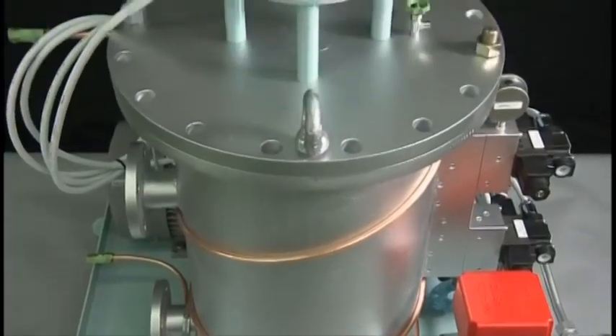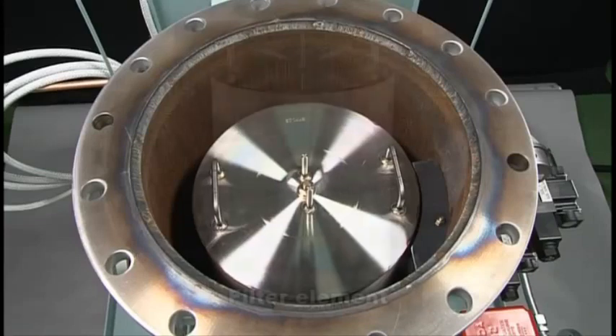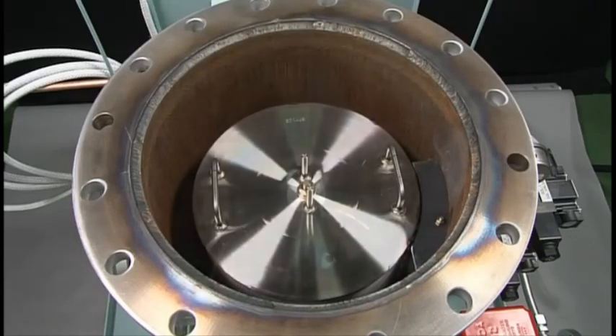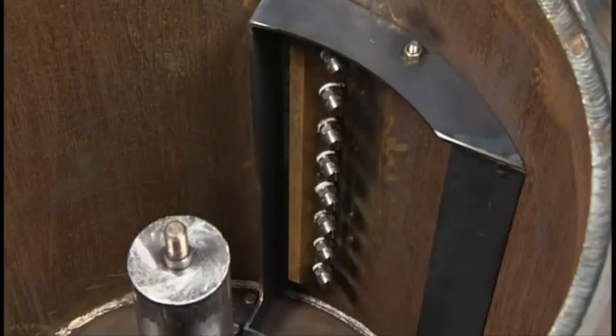Therefore, the latest filters have a mechanism that washes the filter elements automatically to prevent the degradation of filtration performance. This mechanism squirts filtrate onto filters at high pressure to detach and dissipate sludge.